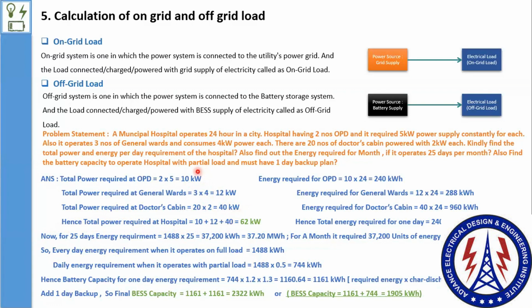Similar to this, we need to draw out the energy requirement. Energy required for OPD, since it has 10 kilowatt power into operational time of 24 hours, is 240 units. Energy required for general wards, 12 into 24, is 288 units. Energy required for doctor's cabin, 40 into 24, is 960 units. Have you calculated this?